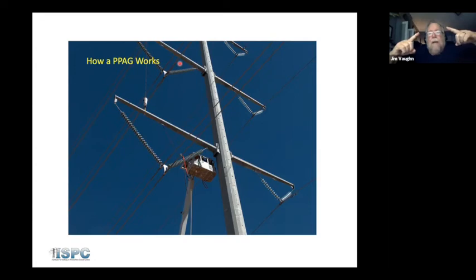And that's an air gap. And the idea is that if there is a high voltage, before it would burn through the wood, it would flash over the air gap. Now, the problem with air gaps is that unlike arresters, the air gaps will have a 60 hertz follow, which means that you may have a high voltage, high frequency flashover on the air gap, but it's going to arc over and it's going to arc to ground and it's going to trip the circuit. So that makes engineers and operators very, very opposed to the use of air gaps.